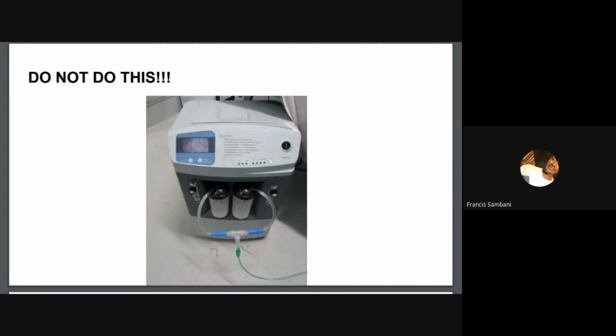You're also not supposed to T the two outputs of the dual flow oxygen concentrator together to get 10 liters per minute of oxygen, as shown in the graphics. Let's say you want 10 liters to supply to, maybe, a COVID-19 patient. What you should do in that case is just get another oxygen concentrator, preferably of the same model, because of output pressure.